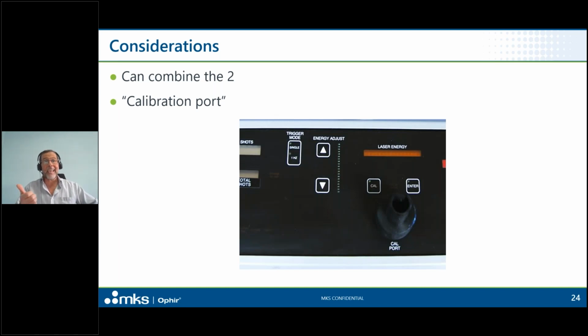The operator will take the handpiece of the laser system, stick it into that cal port, fire the laser. The system is going to measure the full power of the beam as it arrives in the target space, compare that to what it thinks the full power should be based on what the small internal sensor is reading, and then it automatically self-calibrates its laser drive and all the other internal parts of the system, and the ongoing measurements are looking at a small sample of the power. Once every X time, it'll compare itself to what actually arrives at the target, and it'll make its own internal adjustments. So it has that fast feedback control of the process, and it periodically resets itself so that it's correct.